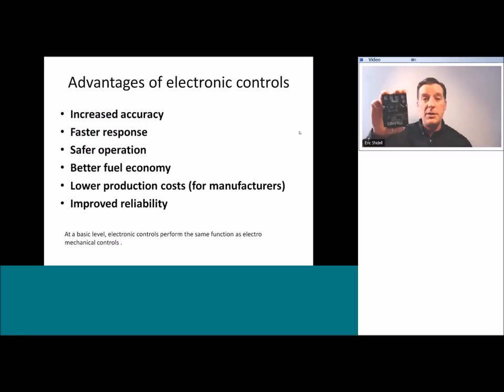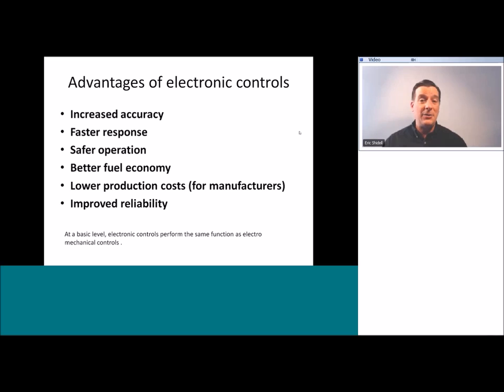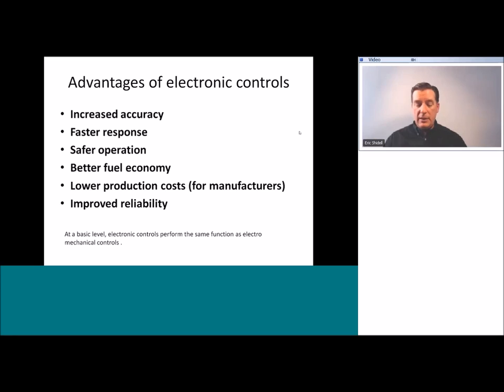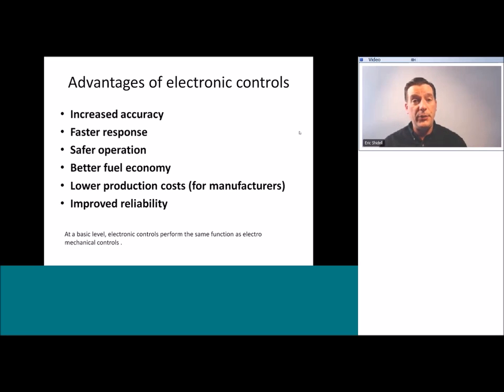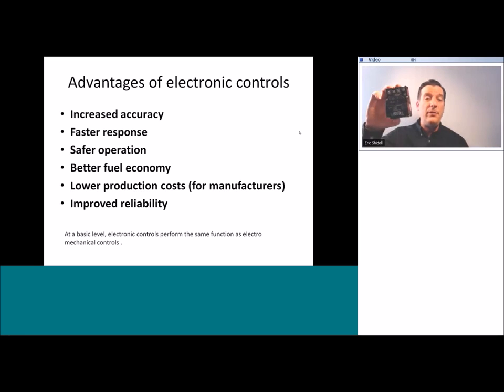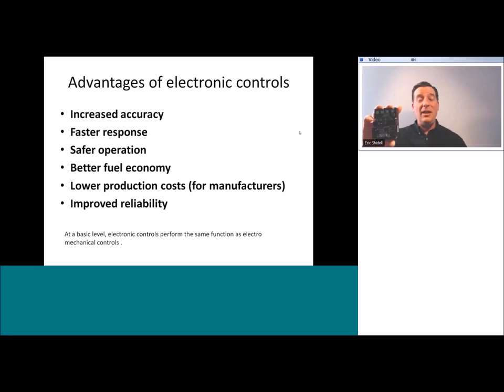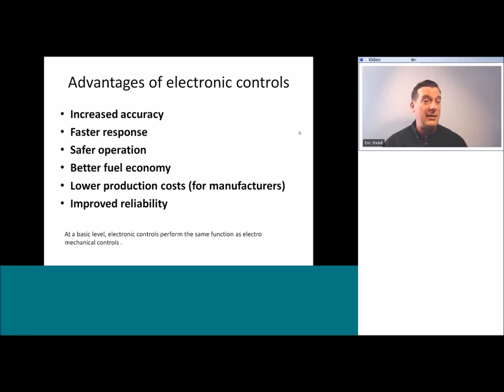One big difference is cost — this retails for about $115, which is a lot more expensive than a traditional contactor. But you get a whole lot more value out of it. One thing it does is provide brownout protection: if the line voltage falls below the nominally acceptable value, that can damage your compressor. This device will sense that and prevent the compressor from trying to energize when the incoming voltage is insufficient. When you realize this device can save a compressor — and potentially a whole freezer or cooler full of food — it's not so expensive anymore.